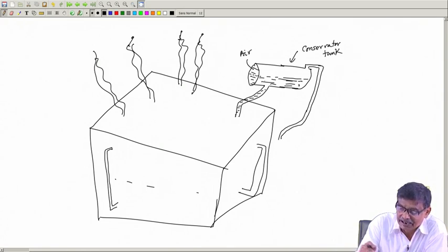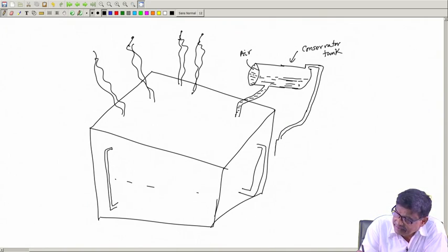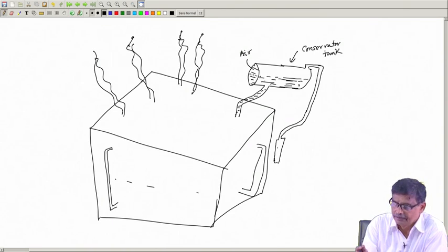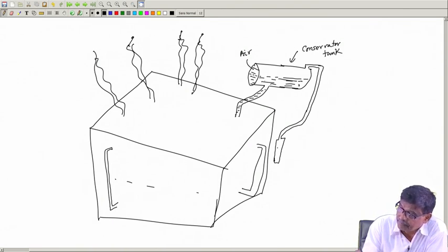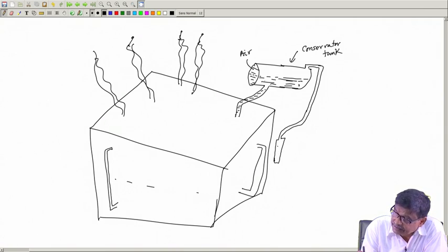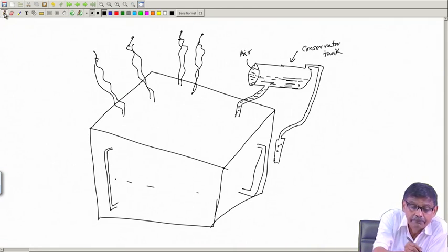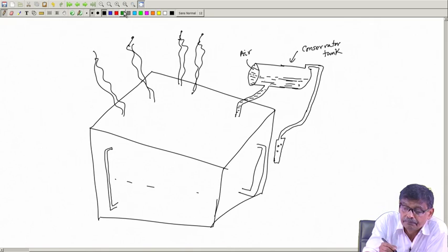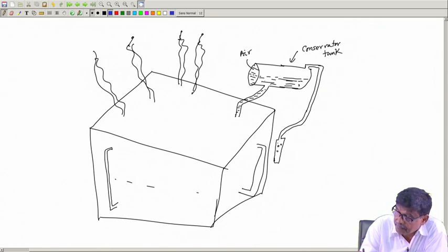Level of oil will change as degree of loading will change, and here is a sort of small vertical vessel like a bottle. Here there will be perforations, and this thing will be filled up with a material called silica gel, a chemical material.